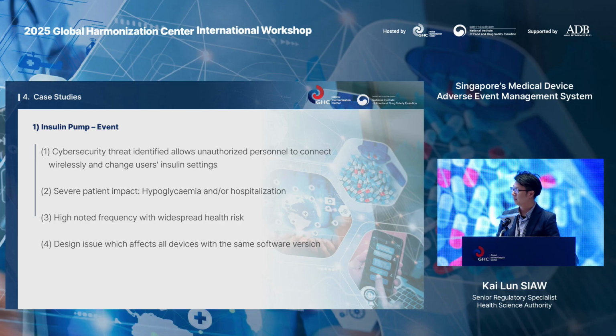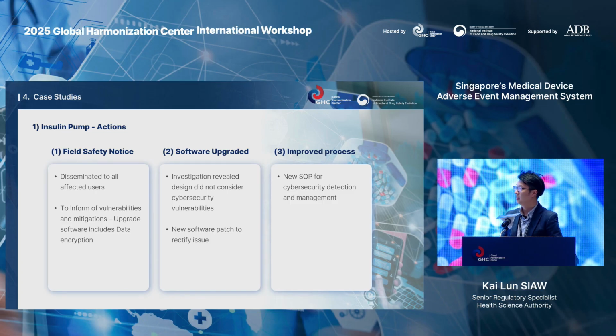So for this, after investigation, we realized that there's a high noted frequency. There's a widespread health risk because the flaw here is actually systemic. It's an issue with the design itself, so it affects all devices using the same software version. So with this, we intervened quickly. What we did was request the company to initiate a field safety corrective action.